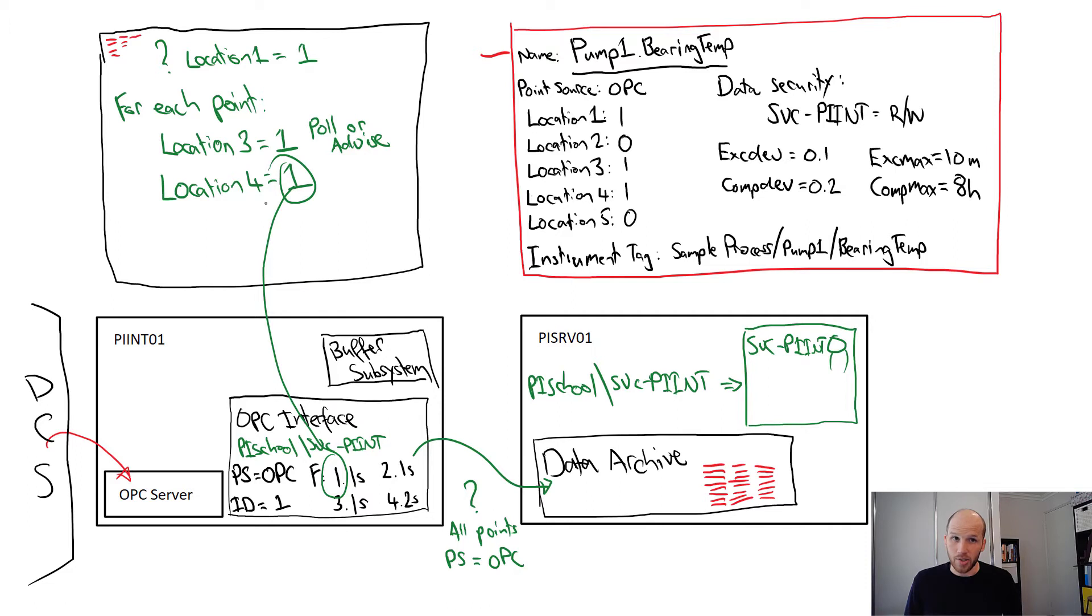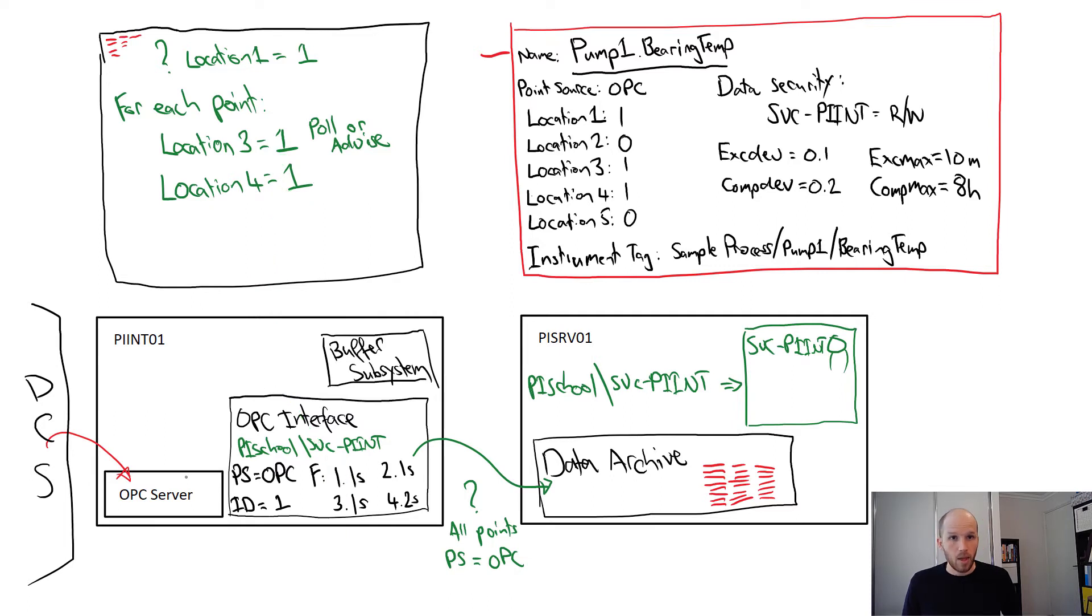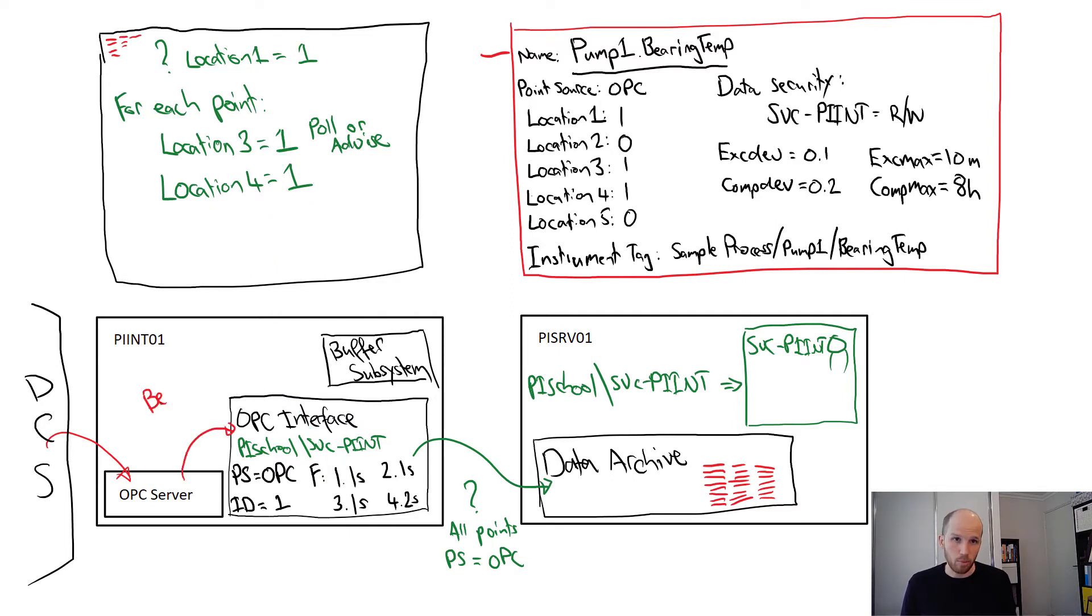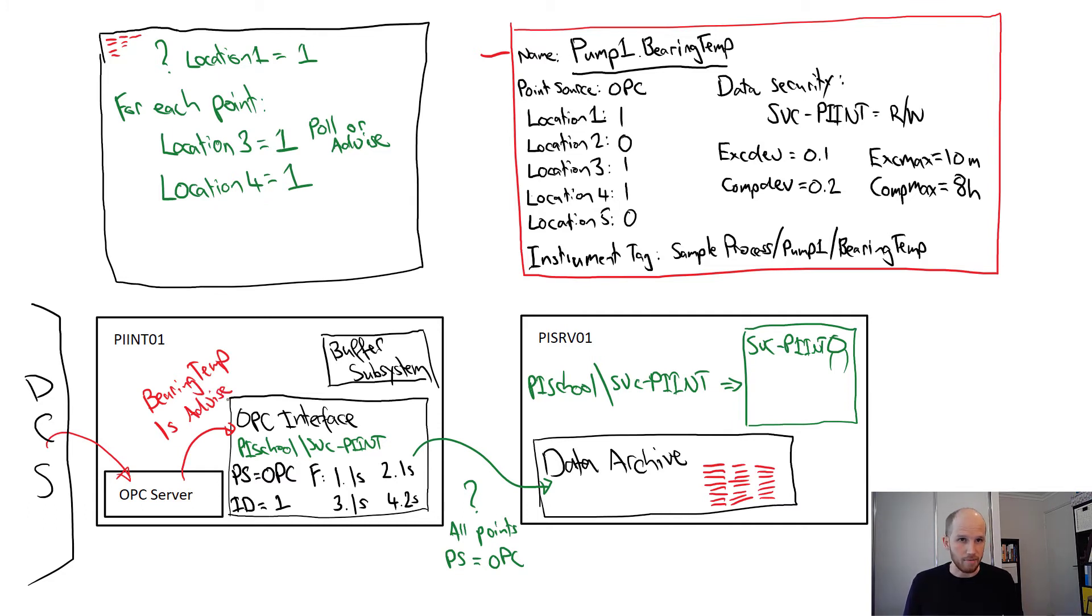Now it has all it needs to know to load the tag. It gets its instrument tag value, and then asks the OPC server, please load the tag with the item ID sample process slash pump 1 slash bearing temp as a 1 second advise point.